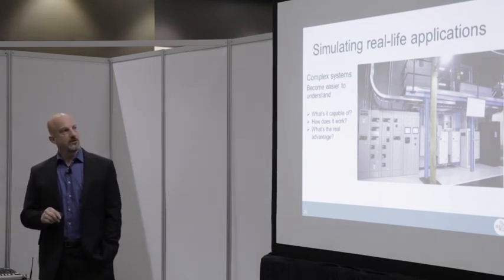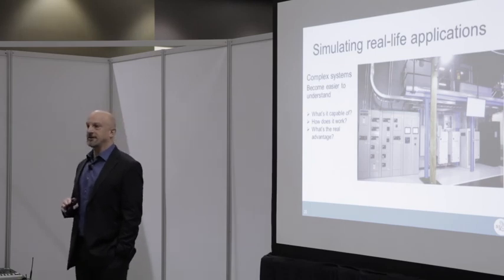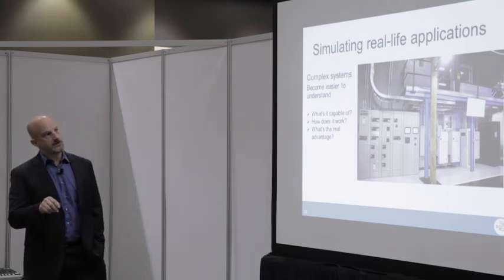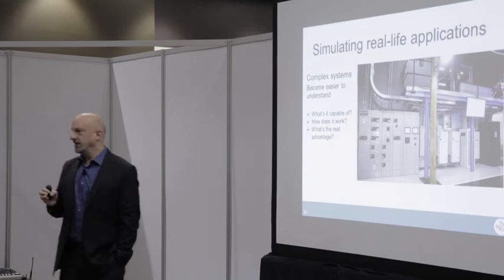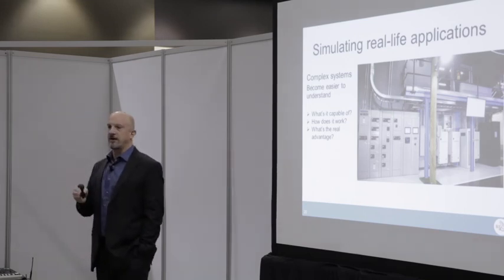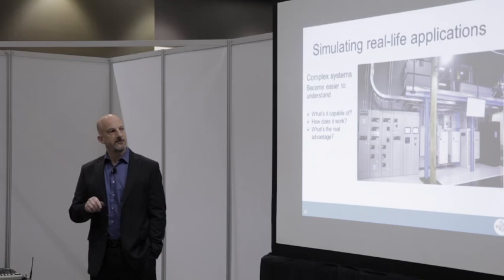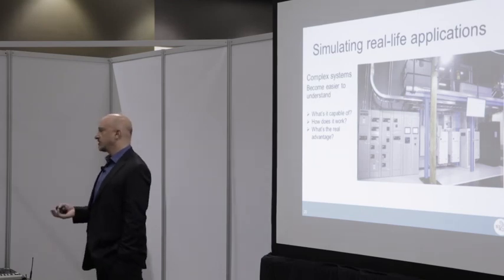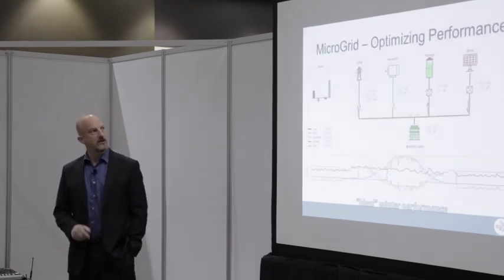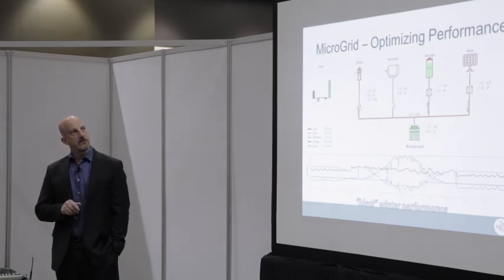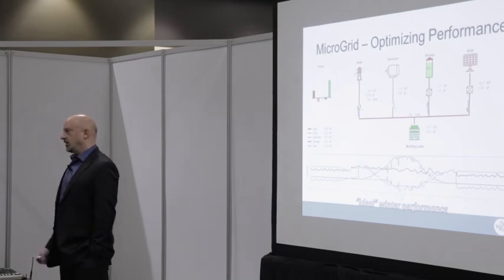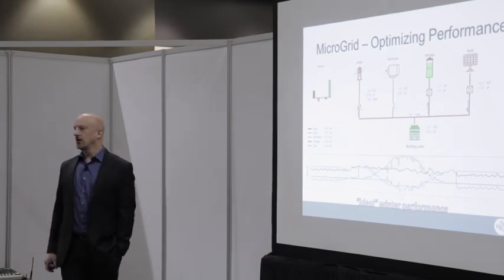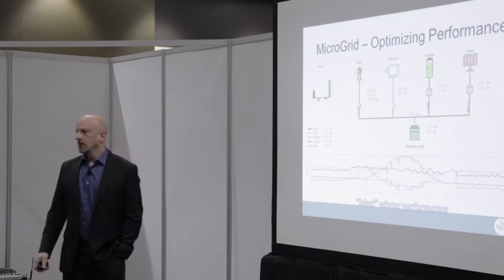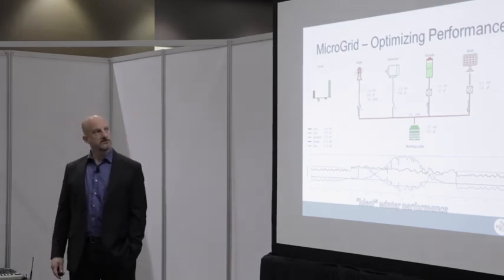This is a full-scale microgrid at 50 kilowatt size, but all of the components here, these little controller boxes, are scaled and set up to run a 5 or 10 megawatt system. We just scaled it for our system here so it shows real data. We have a utility source, a generator source, a battery source, and solar panels. You can have any and all of those, even more, and we can add in wind or anything else.